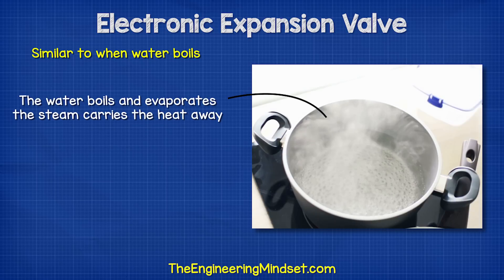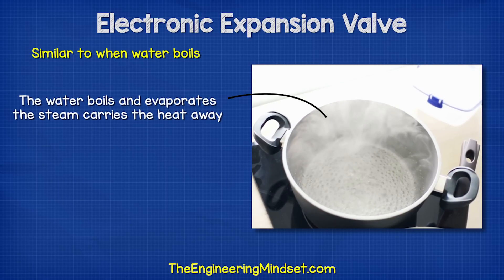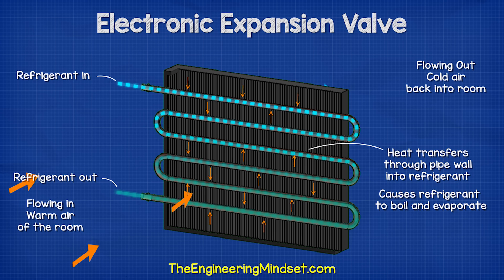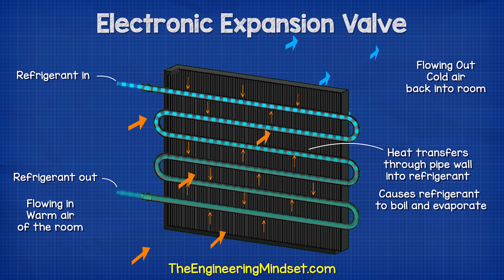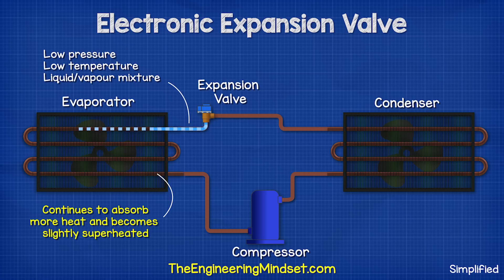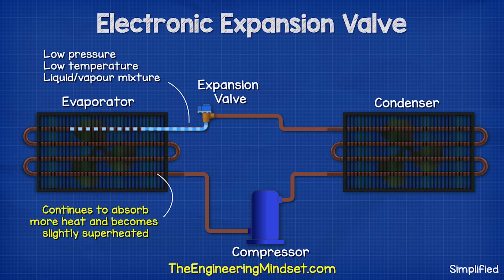As the refrigerant evaporates it carries away the heat. It's similar to when we boil water — the water heats up, it evaporates and turns into steam, and carries this heat away. So the air on the outside is entering hot and it's leaving cold. The refrigerant continues to travel through the evaporator picking up more heat which boils it further until it becomes slightly superheated.